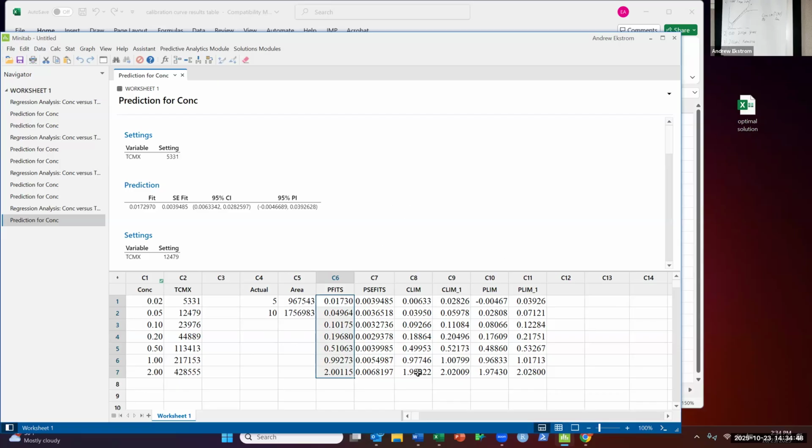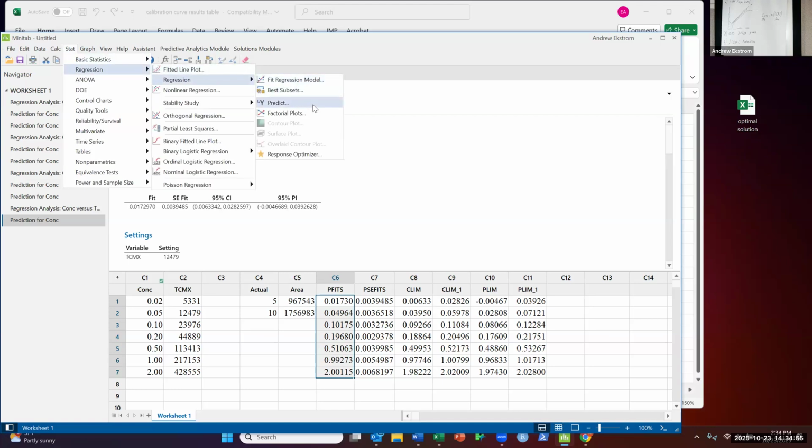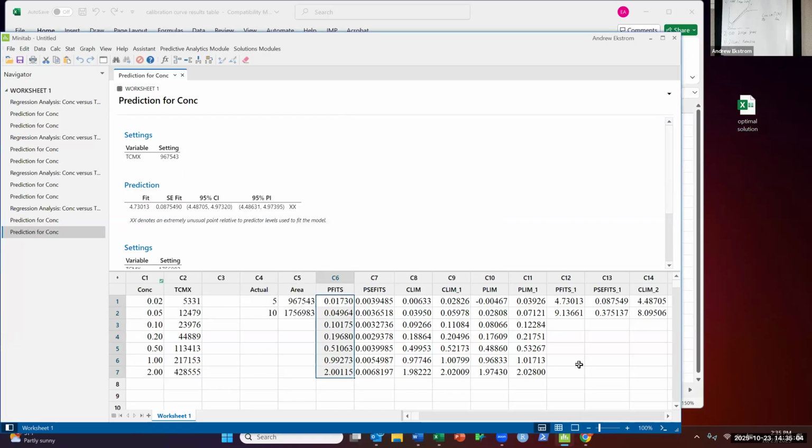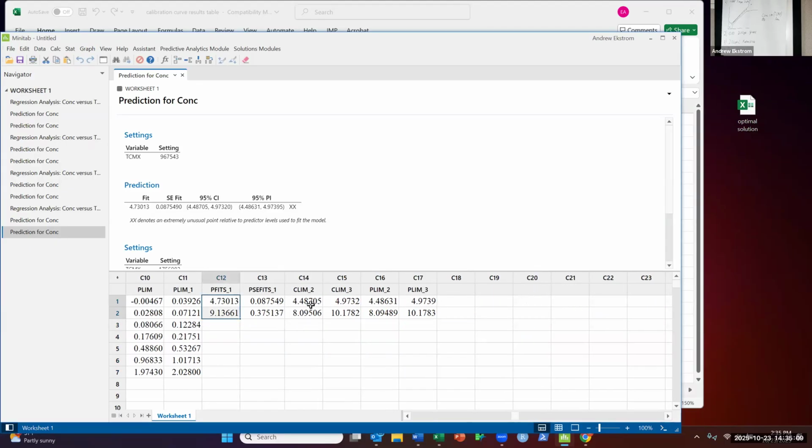And with a model like this, again, we're going to check these last two data points, see if there's anything that changed with that. I don't think there will be, but you never know. And since it is literally that easy to do it, why not do it? So again, the fits are about the same as we had before. It's still a little bit low, predicting the 5.0 ppb standard, but it actually hits the 10 ppb standard.